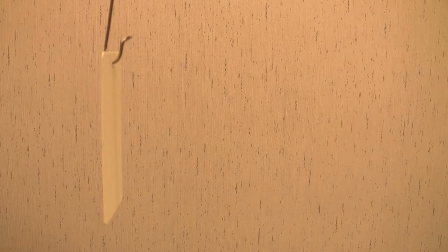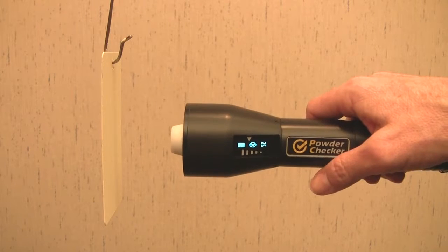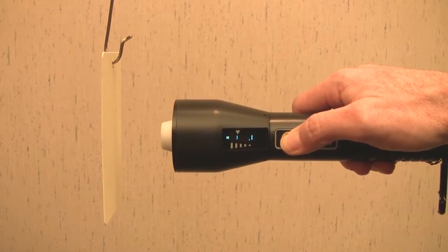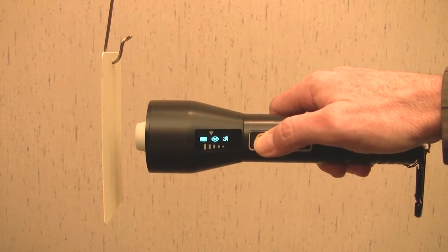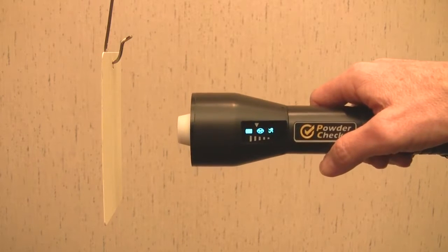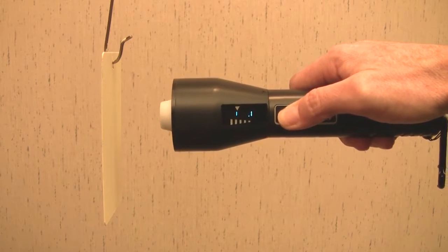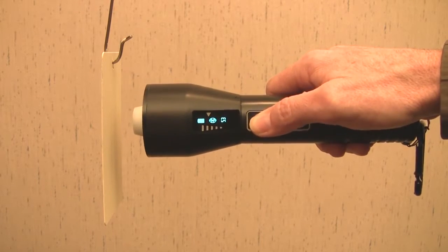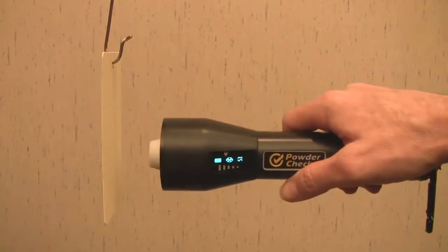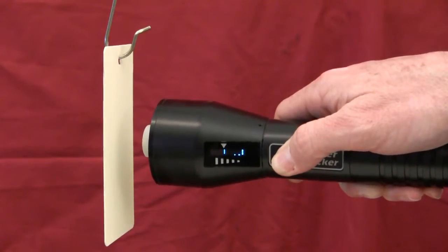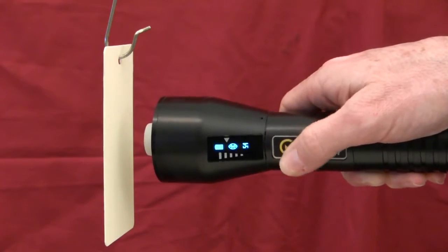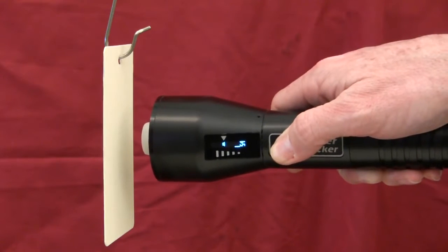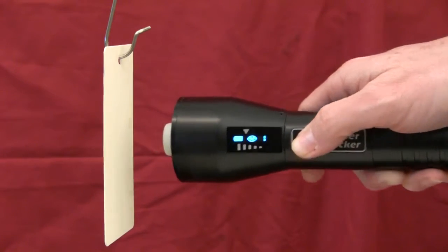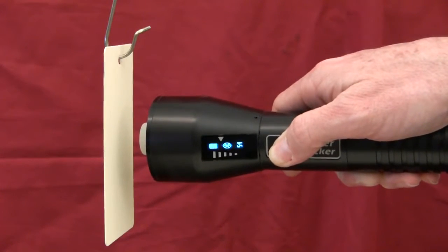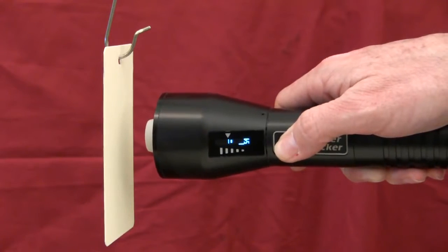Let's look at the step-by-step measurement process. Bring the probe to within 5 centimeters or 2 inches of the coating powder. Press and hold the check button. Bring the probe closer to the powder. While watching the probe display, align the distance paddle with the distance target. After approximately 2 seconds, a cured thickness result appears on both the probe and PosiTector body displays. While the check button is depressed, probe distance and angle should be varied slightly, keeping the distance paddle close to the distance target bar and the amplitude indicator at maximum height. Release the button when you hear a double beep or see a thickness measurement on either display.